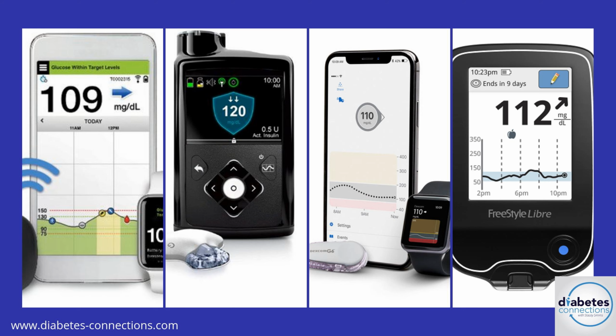The Eversense does require a couple of calibrations per day, and the current sensor is a 3-month model. They've already approved a 6-month version in Europe, and that sensor only requires 1 calibration per day. They're looking at versions that require far fewer calibrations than even that. The FDA seems to take longer than most European safety commissions do, so probably within the next few years, we'll see an Eversense that requires even less work on the patient's part.